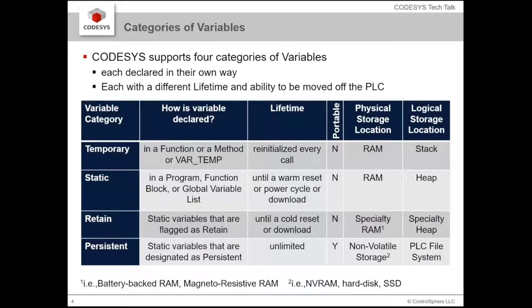You have your retain variables, which are special static variables that have been allocated to a different portion of the heap that's going to be put into a different type of memory — battery-backed memory or magneto-resistive memory or something like that.